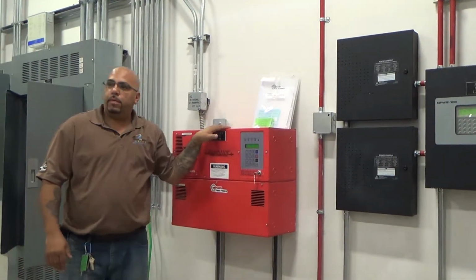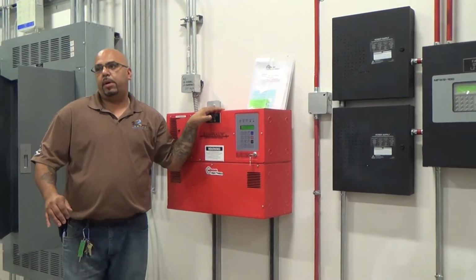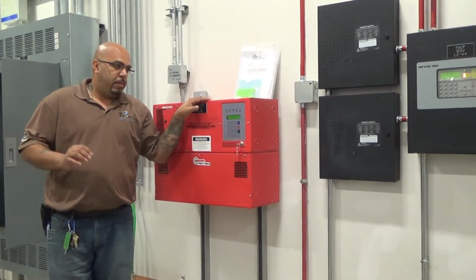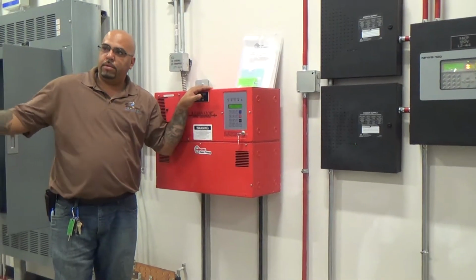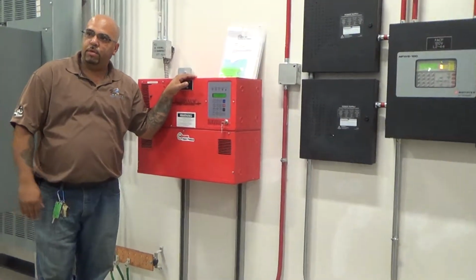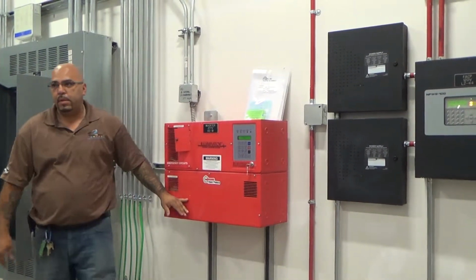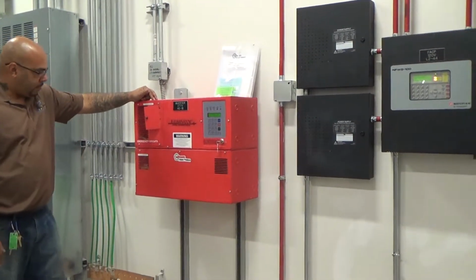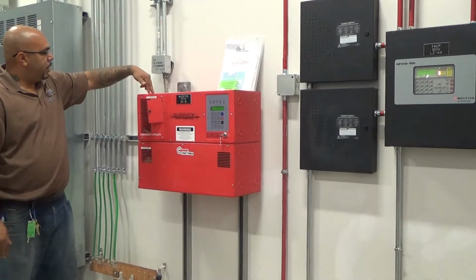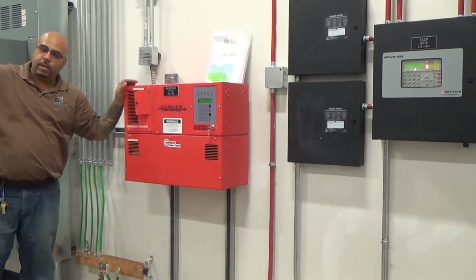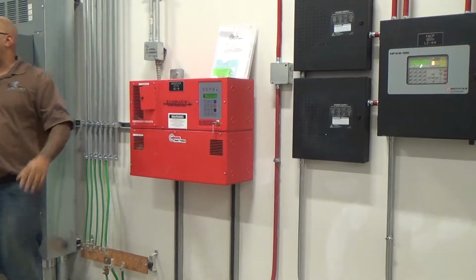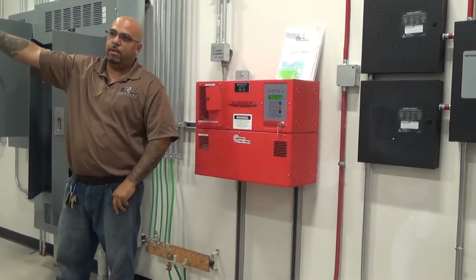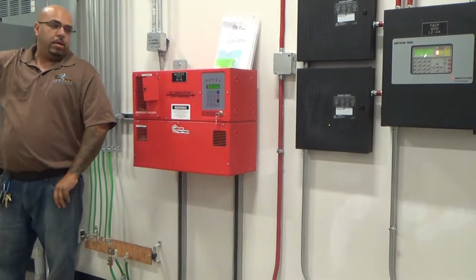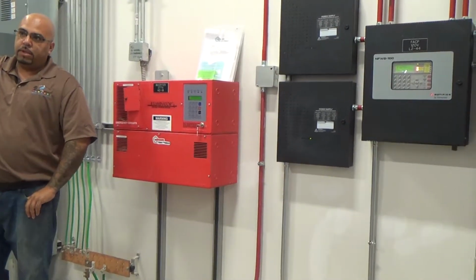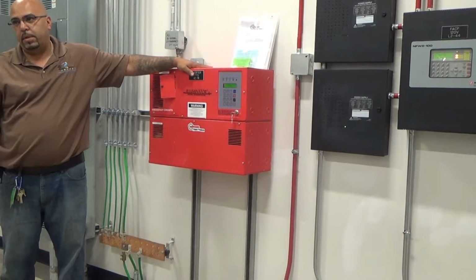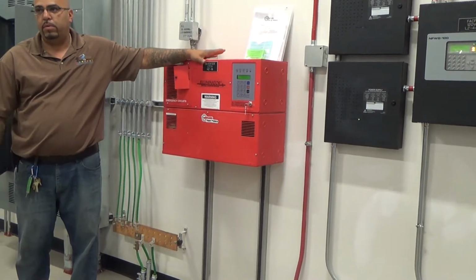The reason that there's an inverter system is because the building is not on generator backup. So for means of egress, you need certain fixtures to go on and off in case we lose power. This is equipped with batteries. We have a direct circuit that feeds this and also goes out to the lights. This particular inverter controls all these pendant lights that are hanging up high here. That's all it controls. Some of them are dedicated for emergency, so that's what this inverter comes in and turns on at that point of losing power.